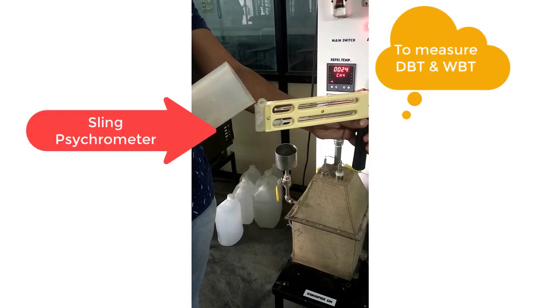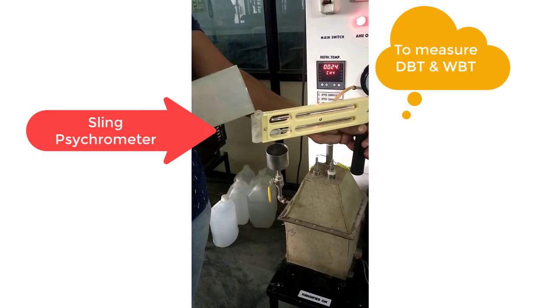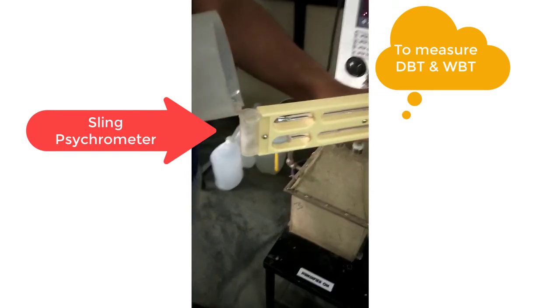So it will generate the steam which flows through the evaporator, in which the air will take the water amount, or we can say the moisture amount, from that steam. So the outlet air has more moisture content as compared to the inlet air. By using a sling psychrometer, we can measure the WBT and DBT of both the inlet side as well as the outlet side.